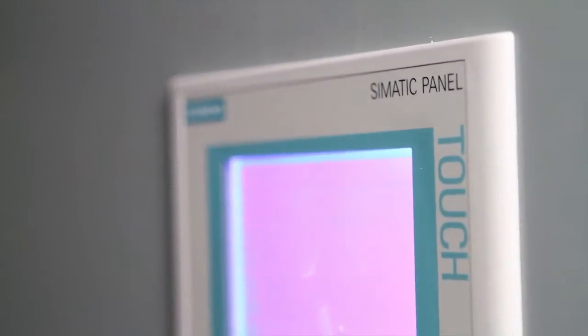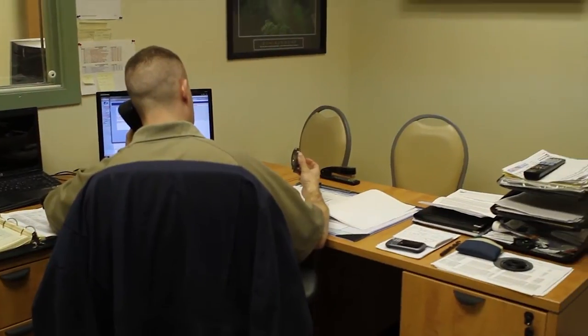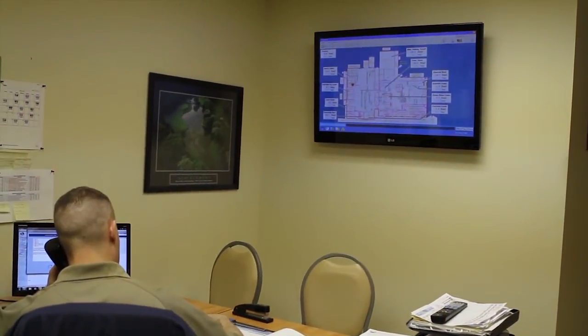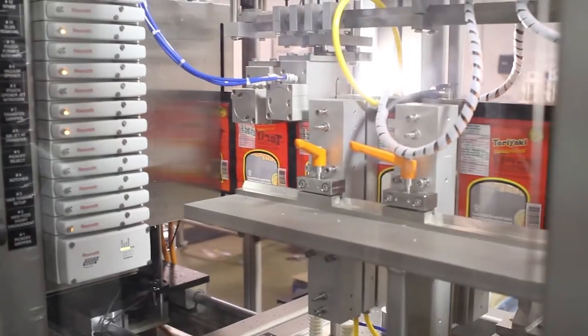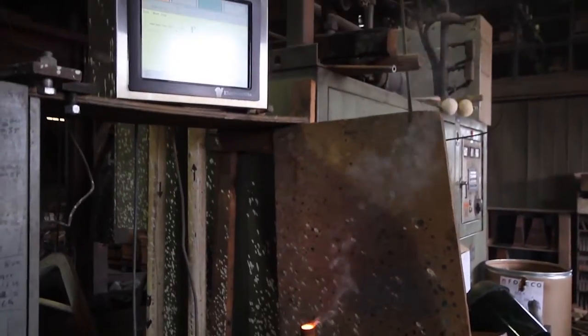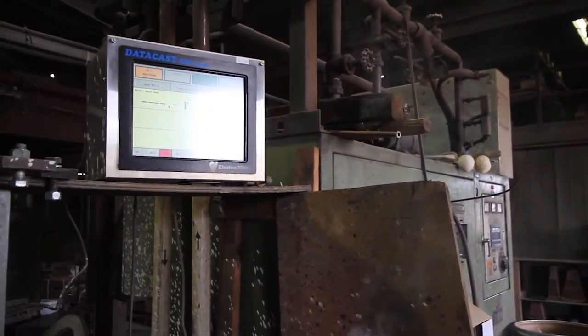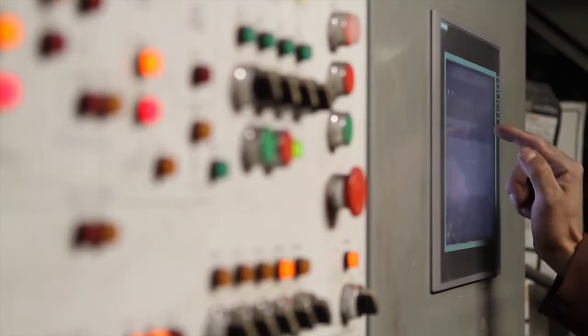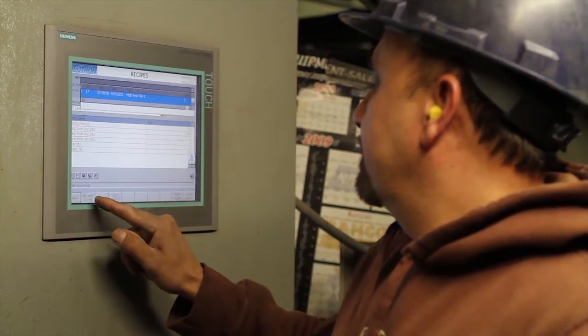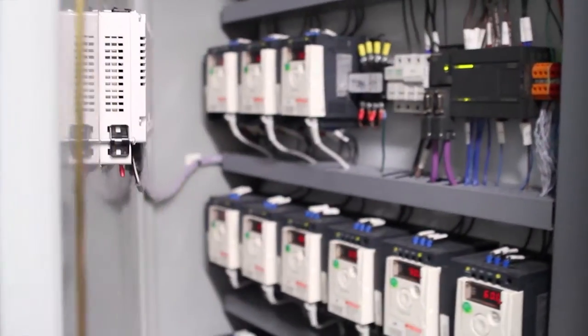When there's a fault that happens, the SCADA system can actually text your phone. It can text your maintenance manager's phone, it can text your contractor's phone and tell them motor M5 on compressor 7A has overloaded. Before they even get to the problem, they know what they're running into.